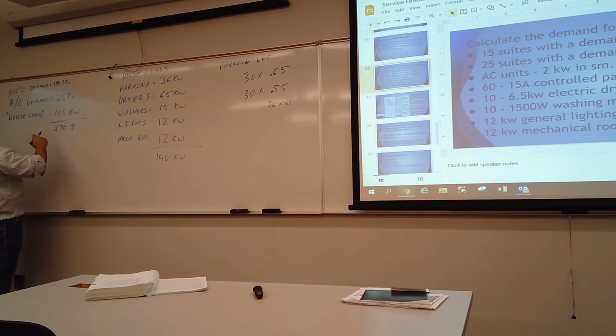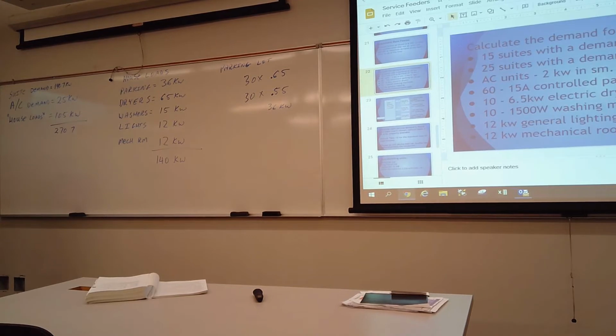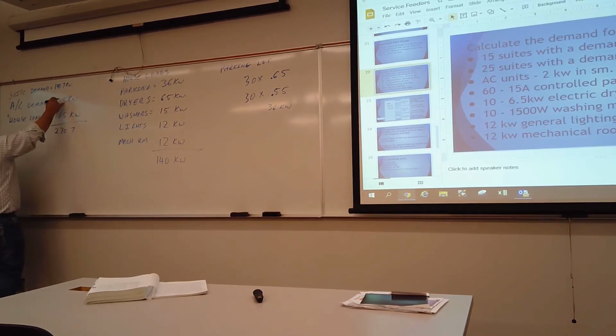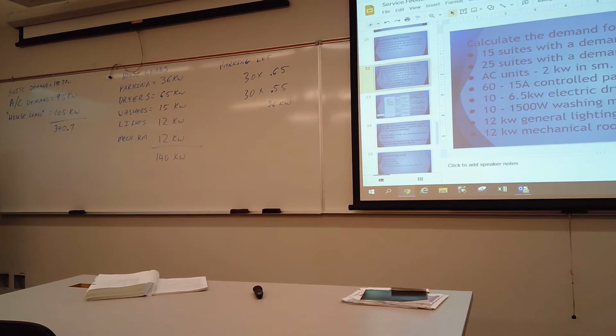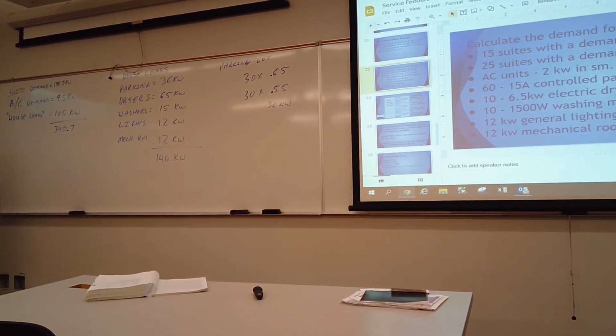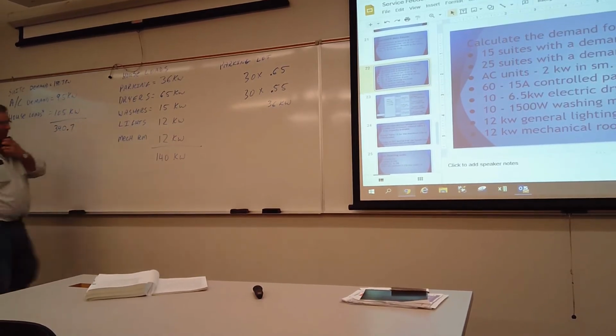Or no, that sounds low. Never mind, 105. Oh, for AC I meant 95, I had 25. Yes, it's AC, it should be 95. AC demand. Why didn't anybody say that earlier? I had it written down, I didn't notice it. 2 times 15 is 30, plus 3 times 25, or 3 times, it was 95, not 25. So with 95, then you're at 340.7. Jeez, you'd think this was my first time. We're watching you. I did that to test you. You guys all failed because nobody said anything. Okay, so we're at 340.7 kilowatts. That's our apartment demand for the whole building.